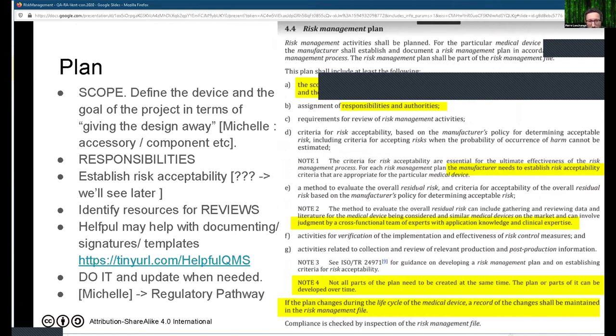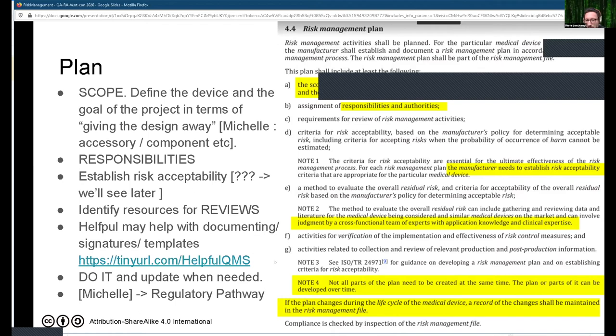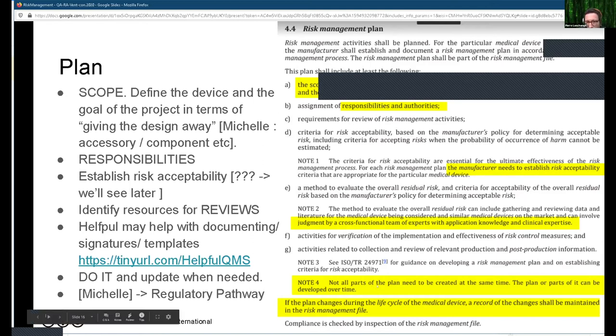You need to establish risk acceptability, which we'll get to later, and identify who will be involved in reviews. I haven't seen many risk management plans so far. You have to do it and update it when needed. Don't avoid it because you think you're not ready — start doing it anyway. Even the standard itself mentions that it's better to start with a partial plan and complement it later than not to do it at all.